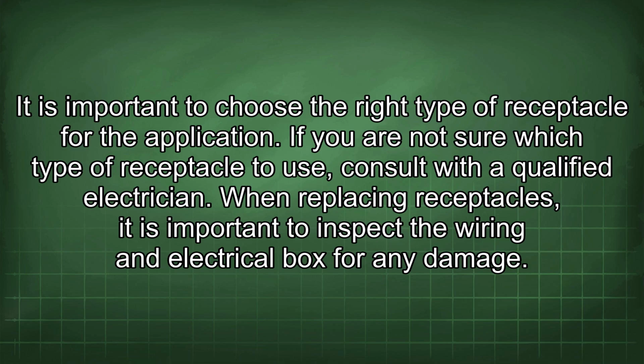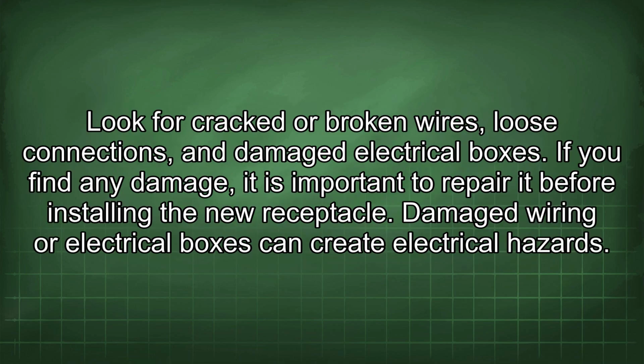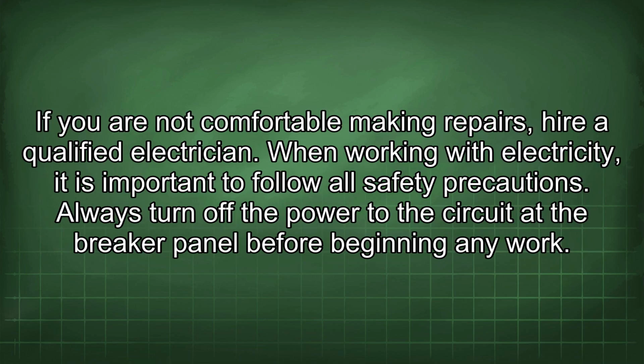When replacing receptacles, it is important to inspect the wiring and electrical box for any damage. Look for cracked or broken wires, loose connections, and damaged electrical boxes. If you find any damage, it is important to repair it before installing the new receptacle. Damaged wiring or electrical boxes can create electrical hazards. If you are not comfortable making repairs, hire a qualified electrician.